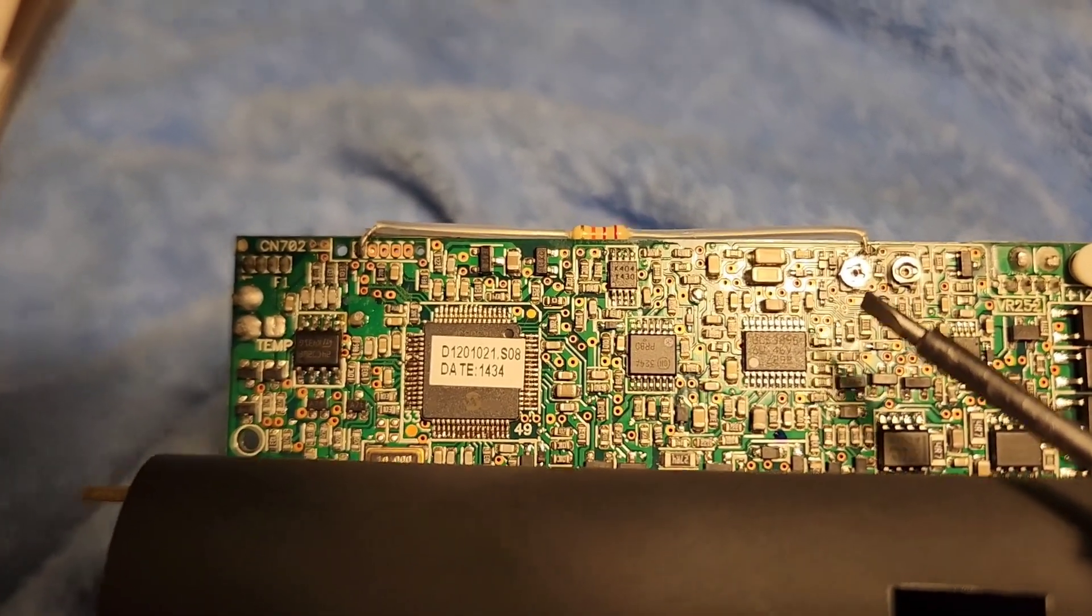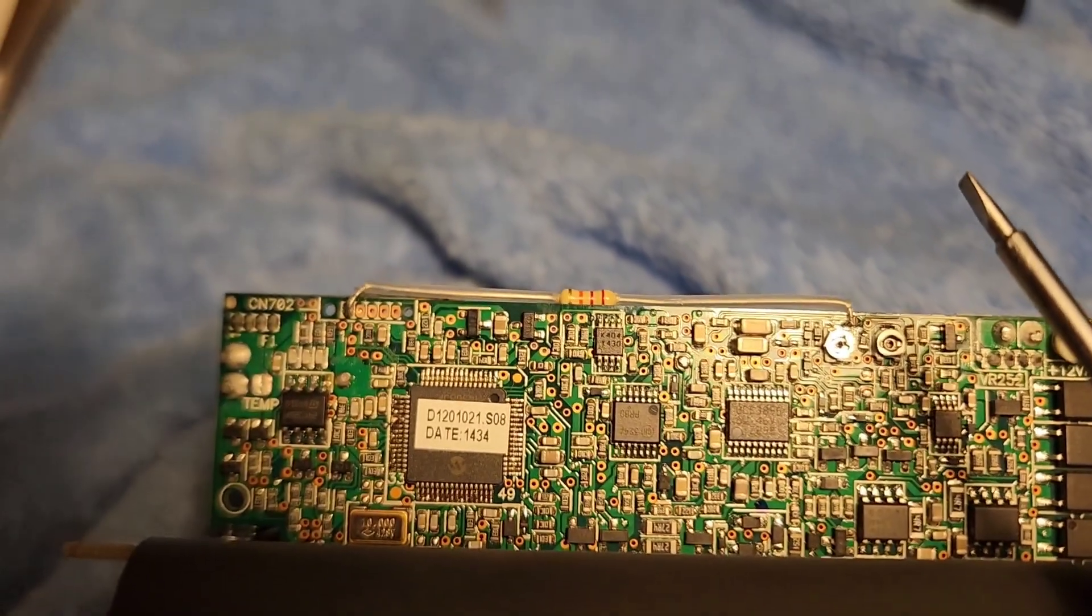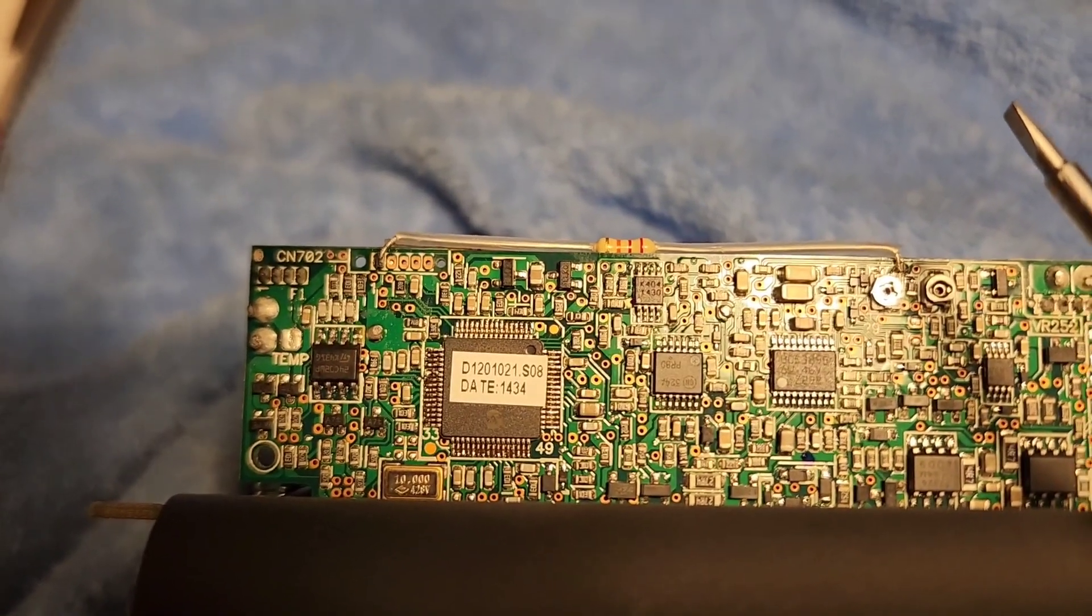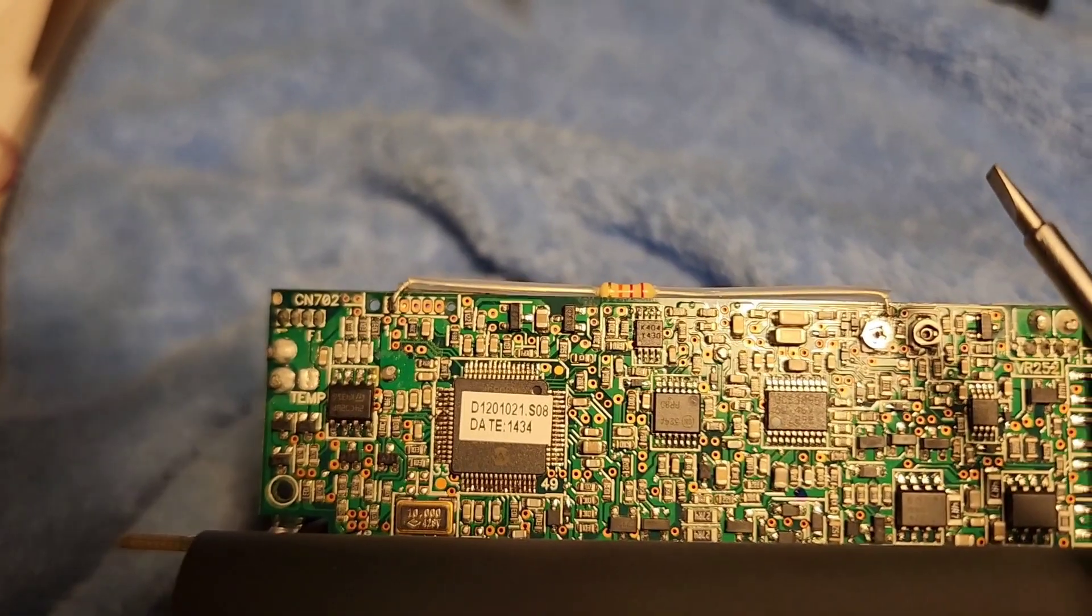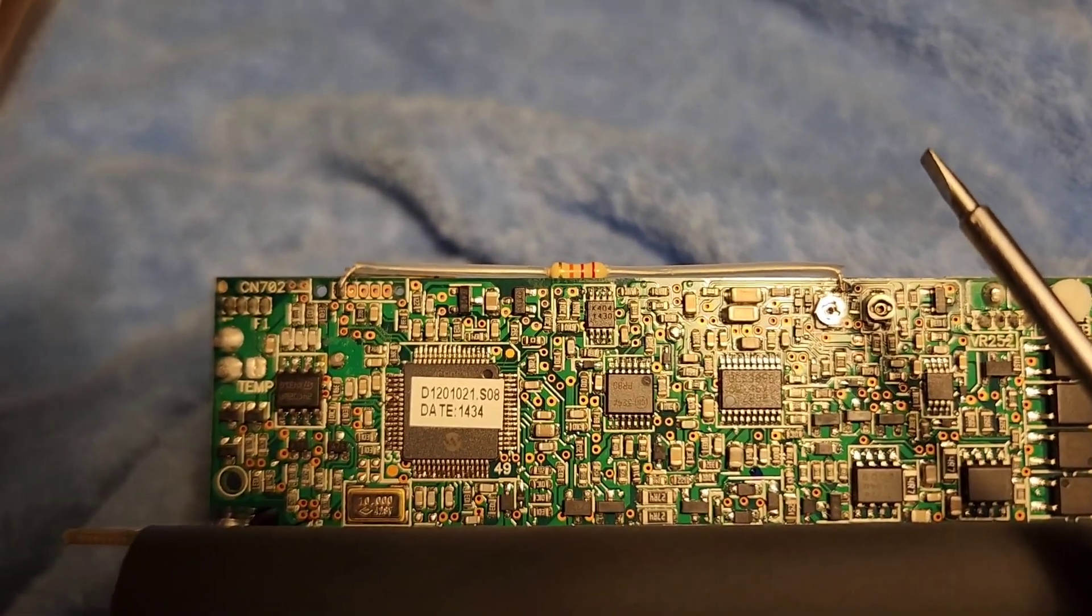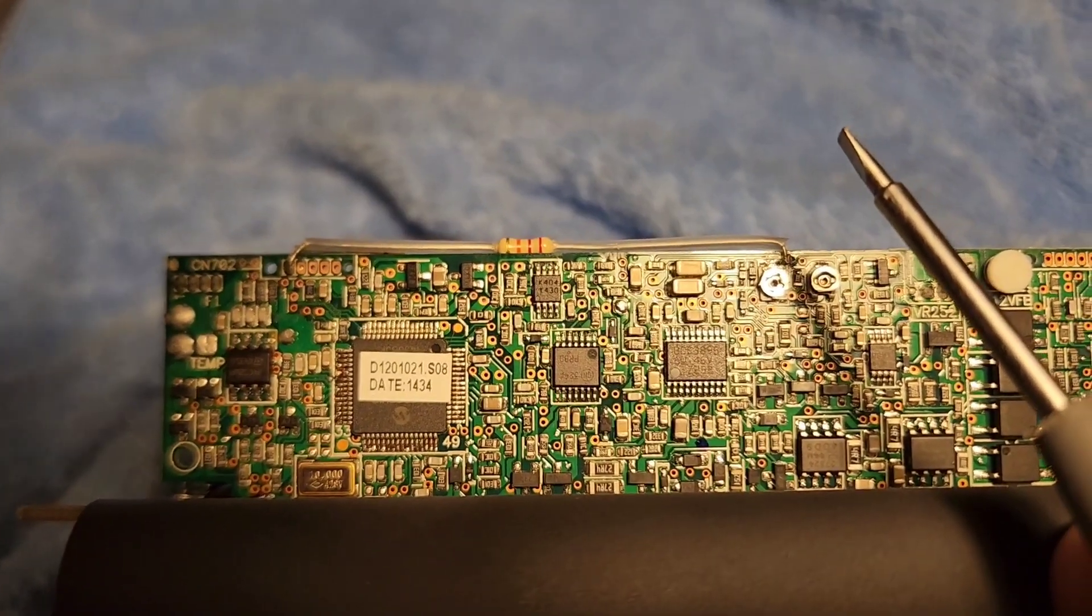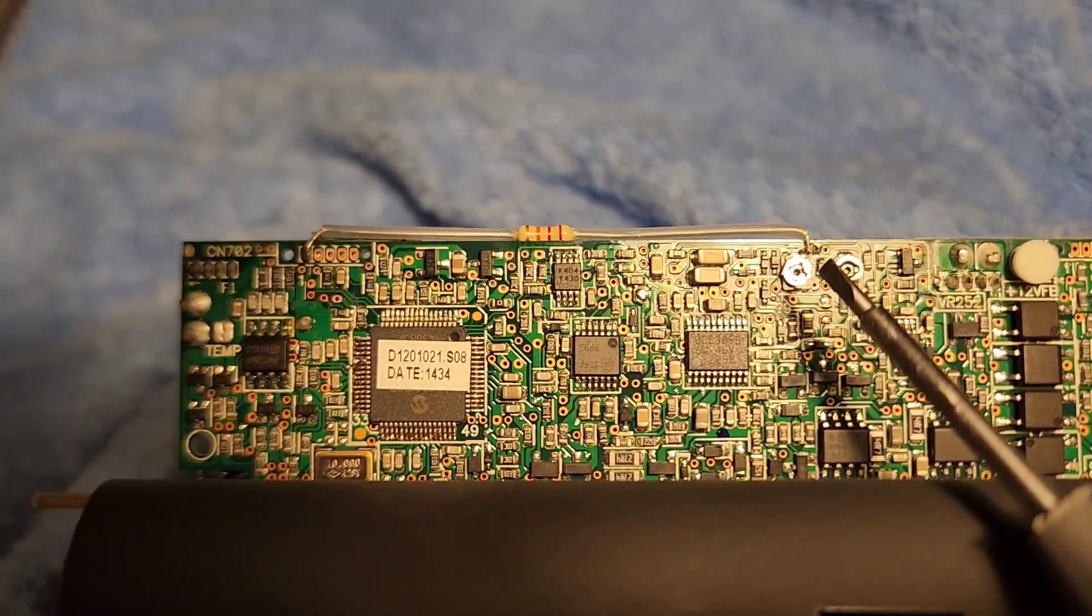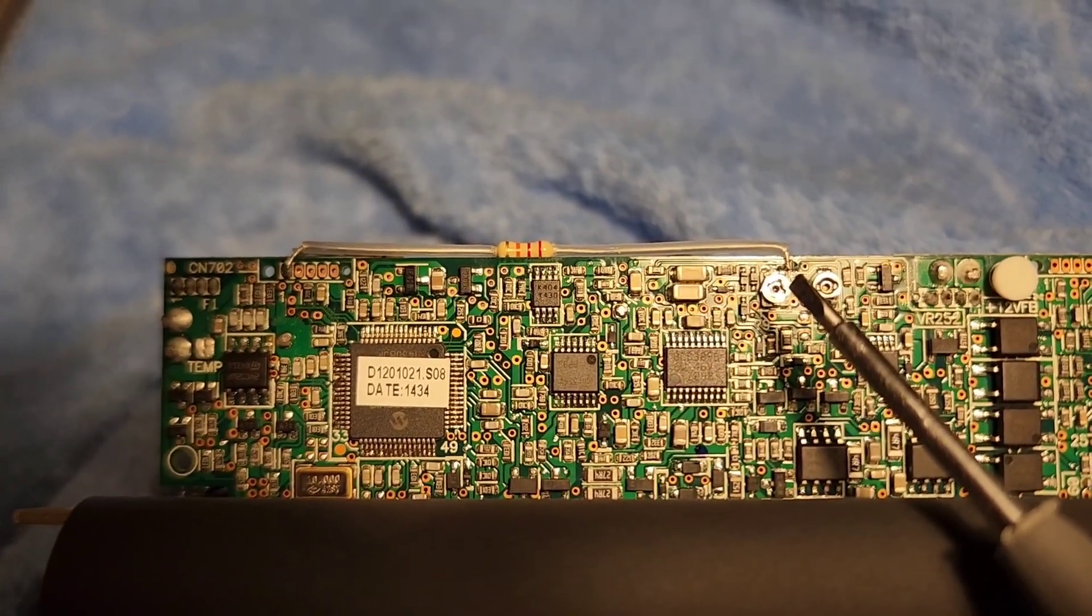I first started off with a 15k and the voltage was 14.8, I believe. It would not come down any lower, I believe it was 14.4. And then I put in an 18k and I was able to get it down to 14.04 was as low as I could get it. I then put in a 22k, which is what's in here right now, and it will go down to 13.84, which is what I have it set at.